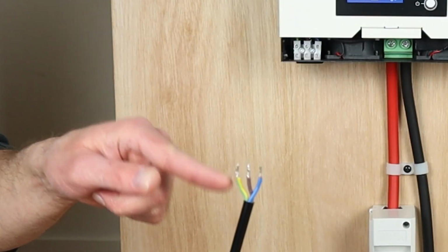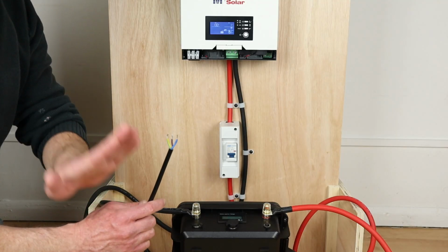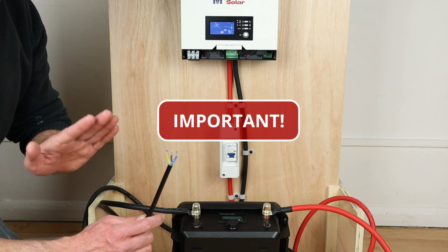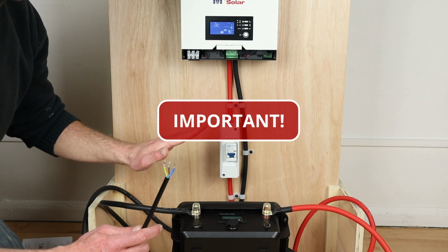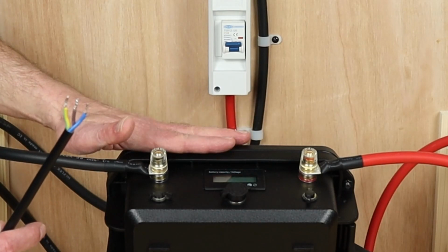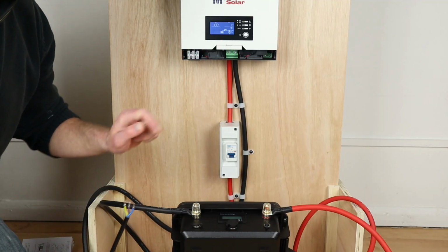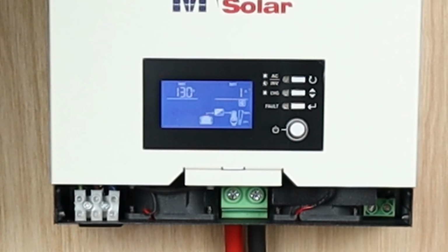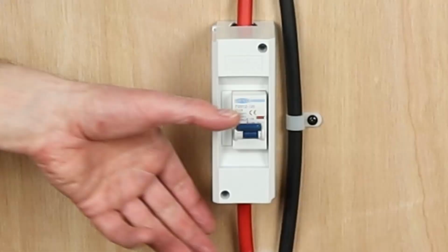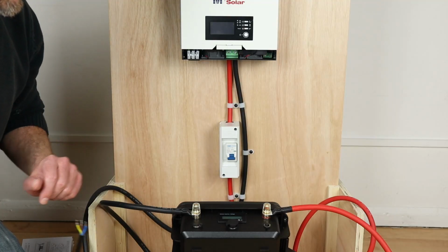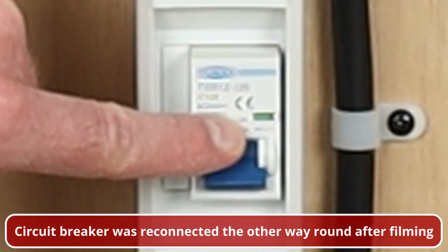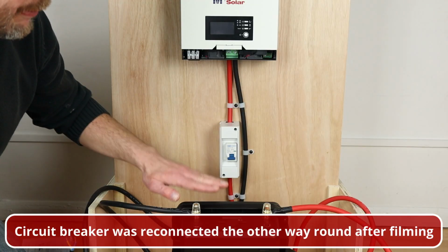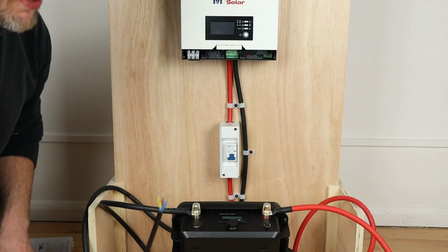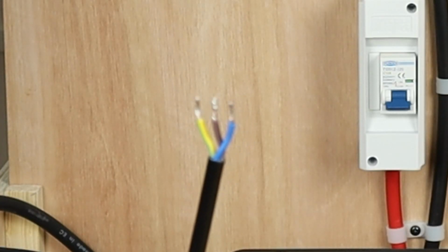Right, before I can connect these wires into this terminal here, I need to stop - this is really important. I need to make sure that everything is switched off, powered down and isolated, so the battery is isolated and the inverter is off. First off, I'm going to switch off the inverter and wait for that to power down. Now I'm going to switch off the circuit breaker - as you can see, it's turned back to green, meaning that's now isolated, meaning the battery is isolated. Now that means I can go ahead and connect these up to the terminal.